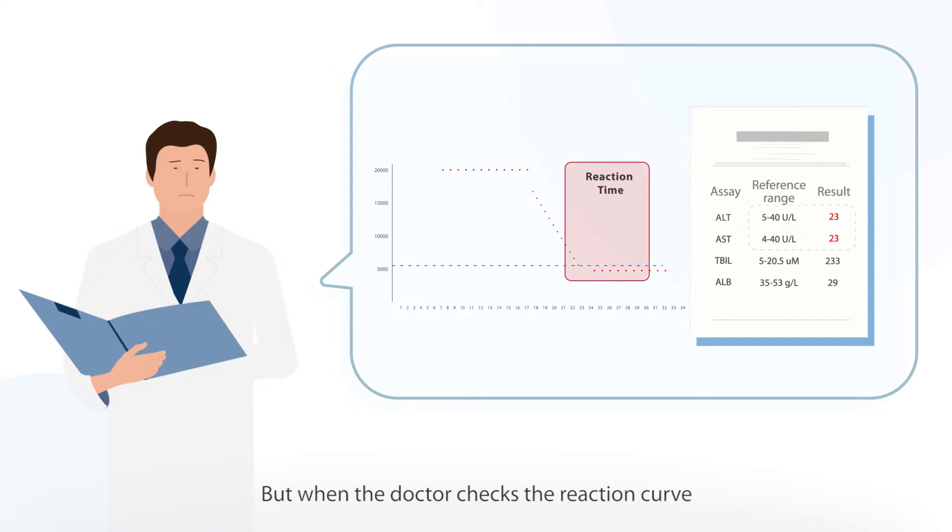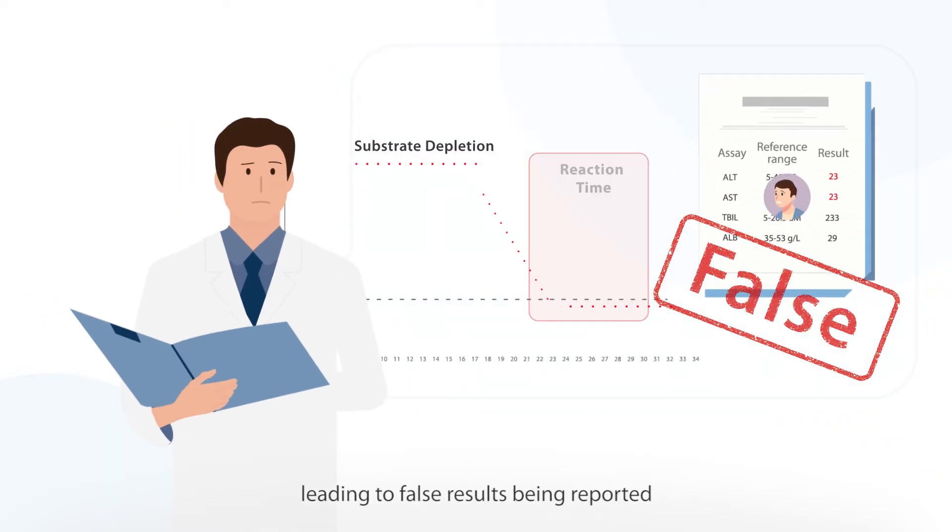But when the doctor checks the reaction curve, it appears that both tests display substrate depletion, leading to false results being reported.